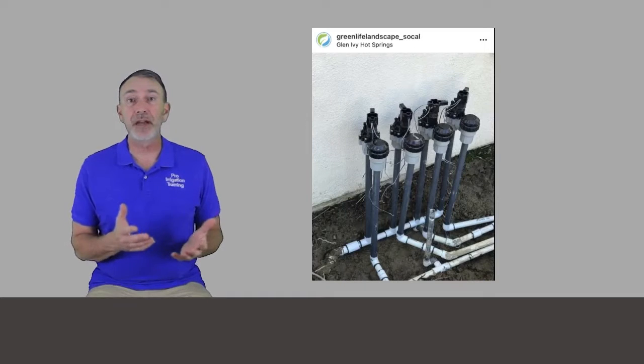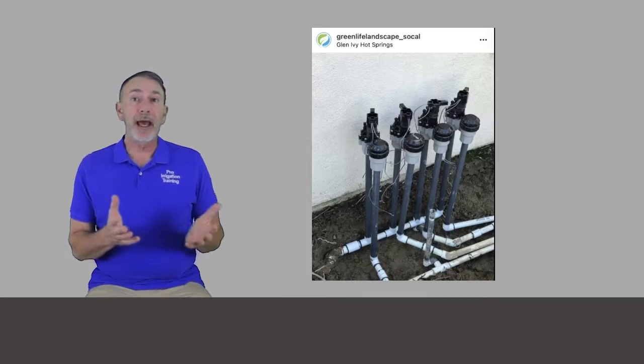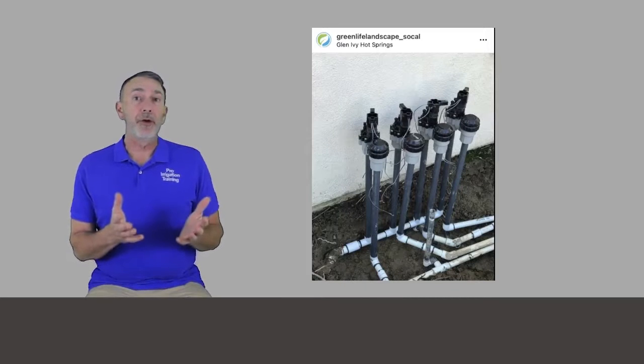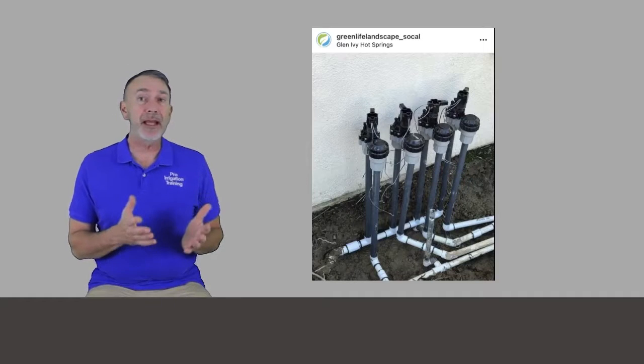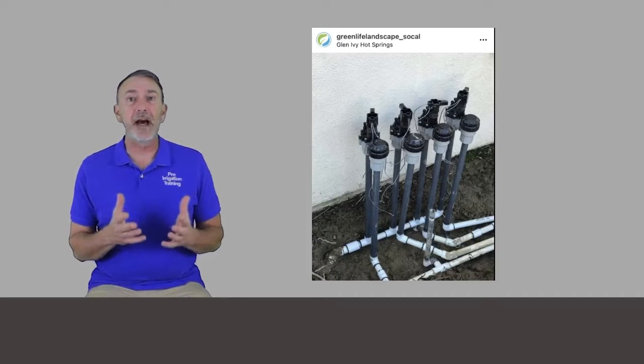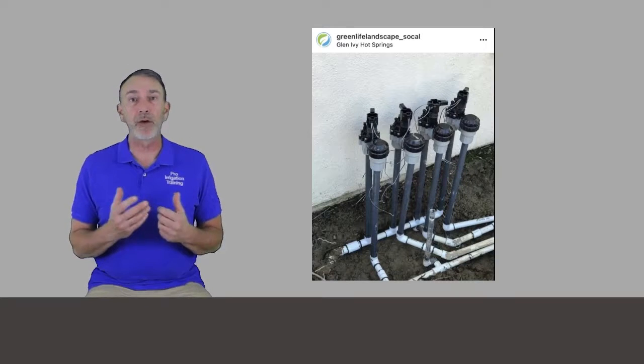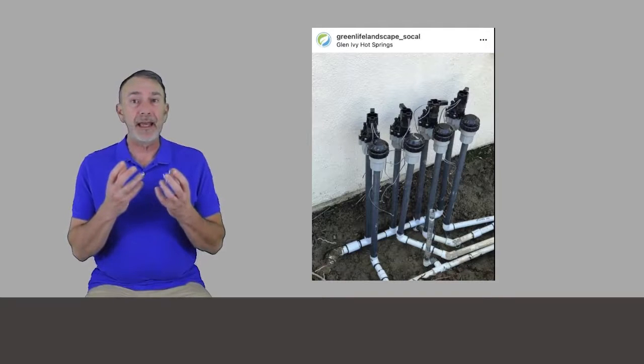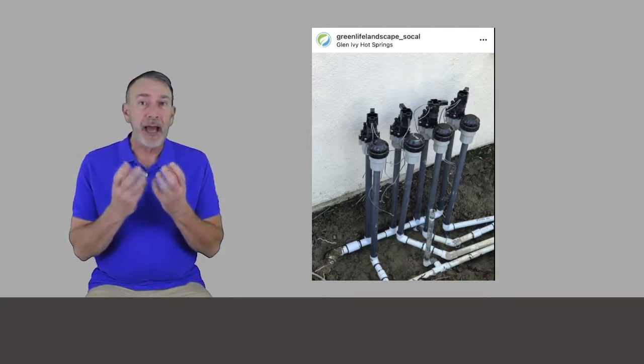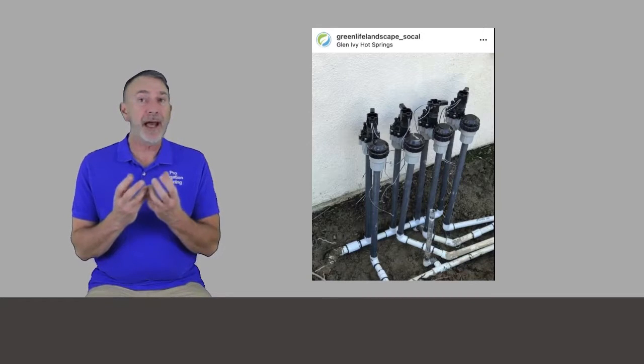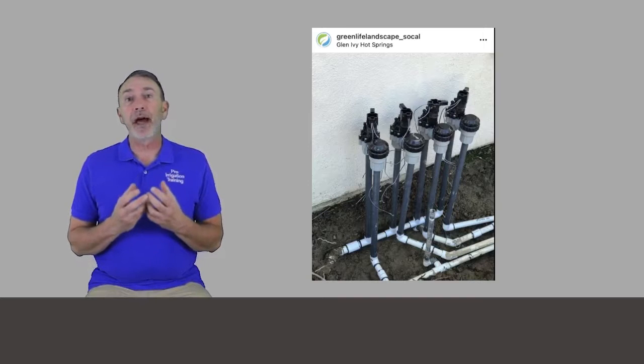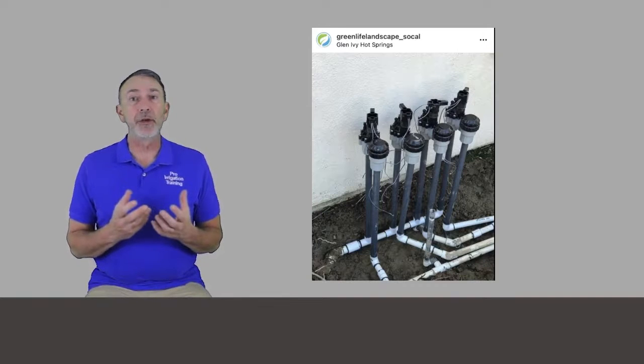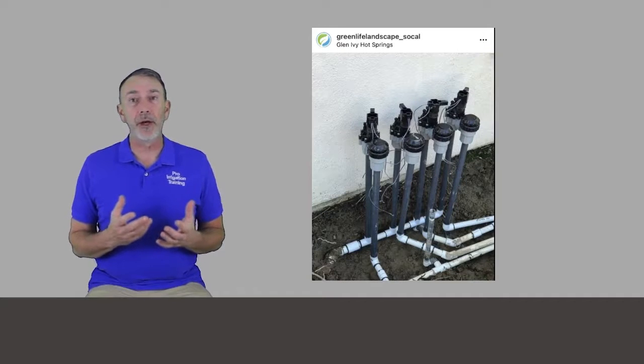The option on that is maybe your state or your city or county requires anti-siphon valves and they don't like the double check valve assembly. So then you wouldn't have your backflow prevention unit at the beginning, then your anti-siphon valves, which is your zone valve, which has an atmospheric vacuum breaker attached to it. That's going to be your backflow prevention unit and that's going to satisfy your local codes.